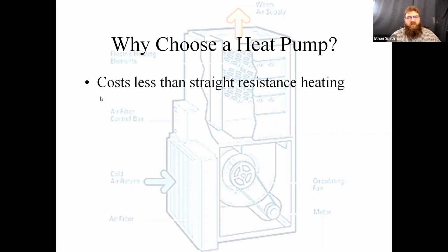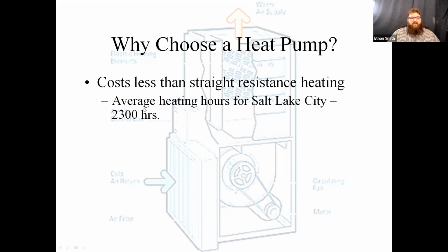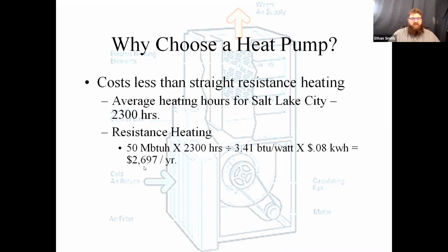So why would we choose a heat pump? Back to that operating cost, it can cost less than straight resistance heating. This is an example for Salt Lake City, where I live. We have an average of 2,300 heating hours per season. For my resistance heating, I have a 50,000 BTU load just to make it easy. We take our formula from that other page, multiply it by 2,300 hours, then divide by 3.41 BTUs per watt. At the time I did this, I was at 8 cents a kilowatt hour. So to heat my house with straight electric would be about $2,600 a year.